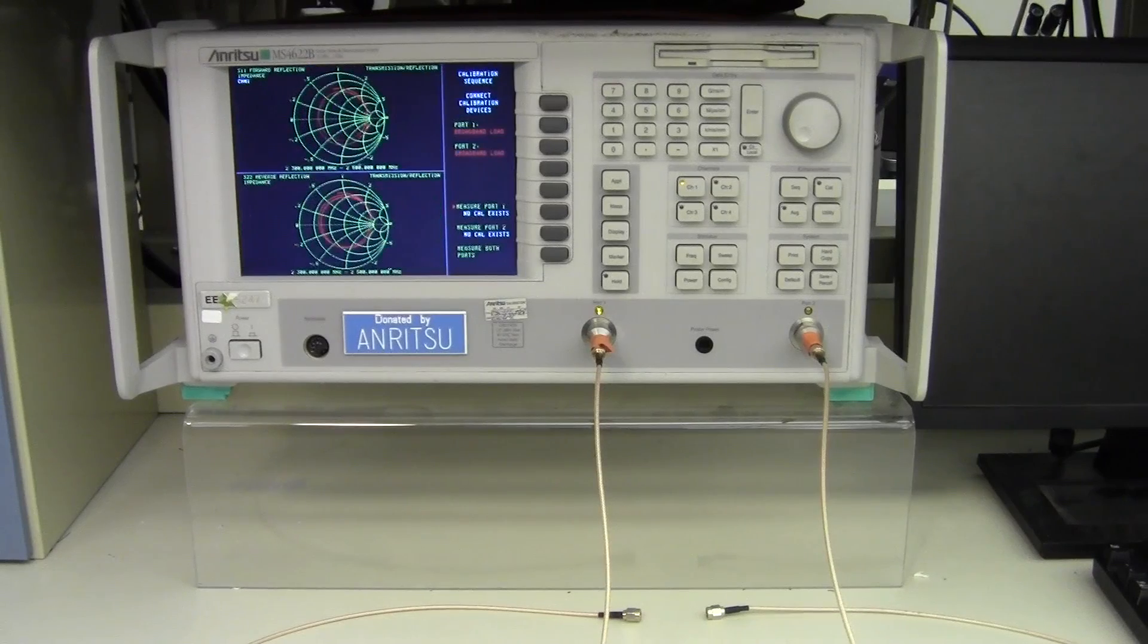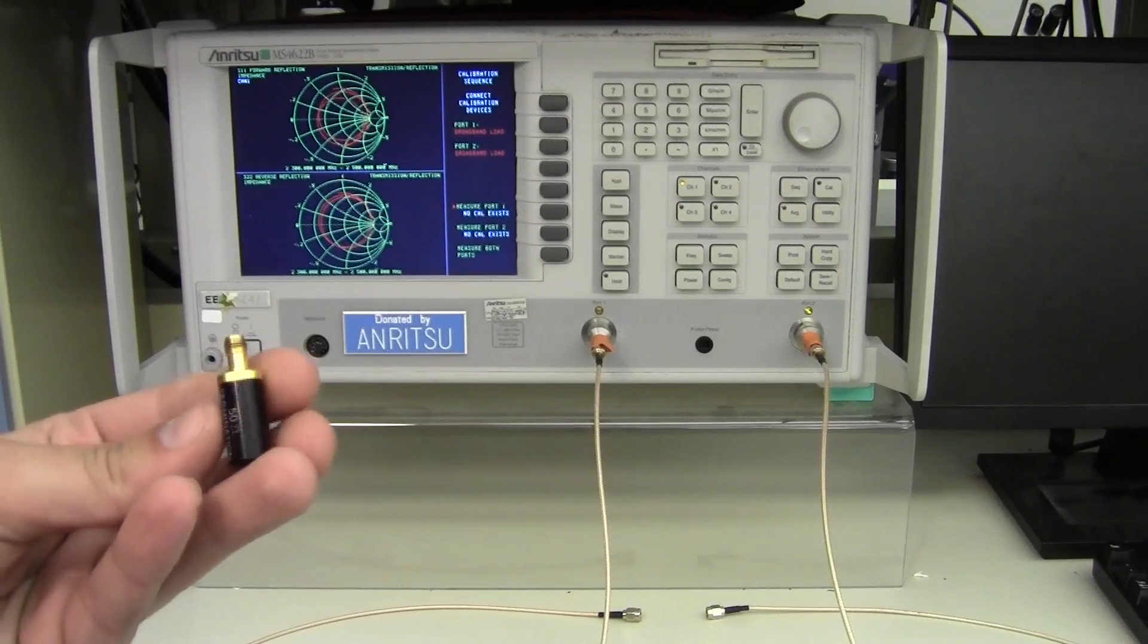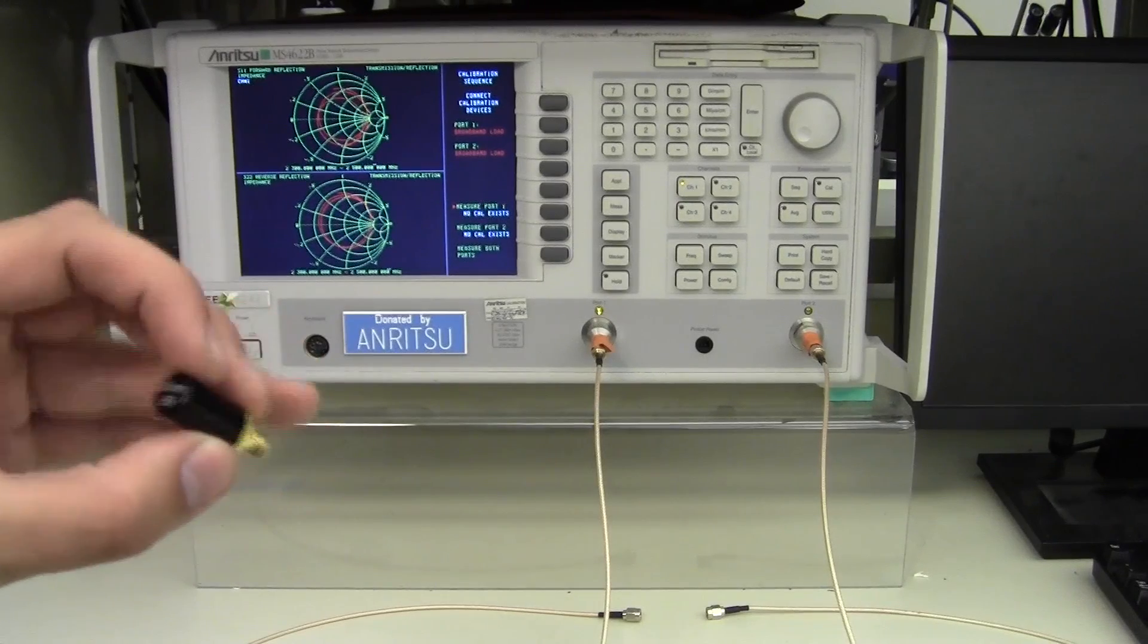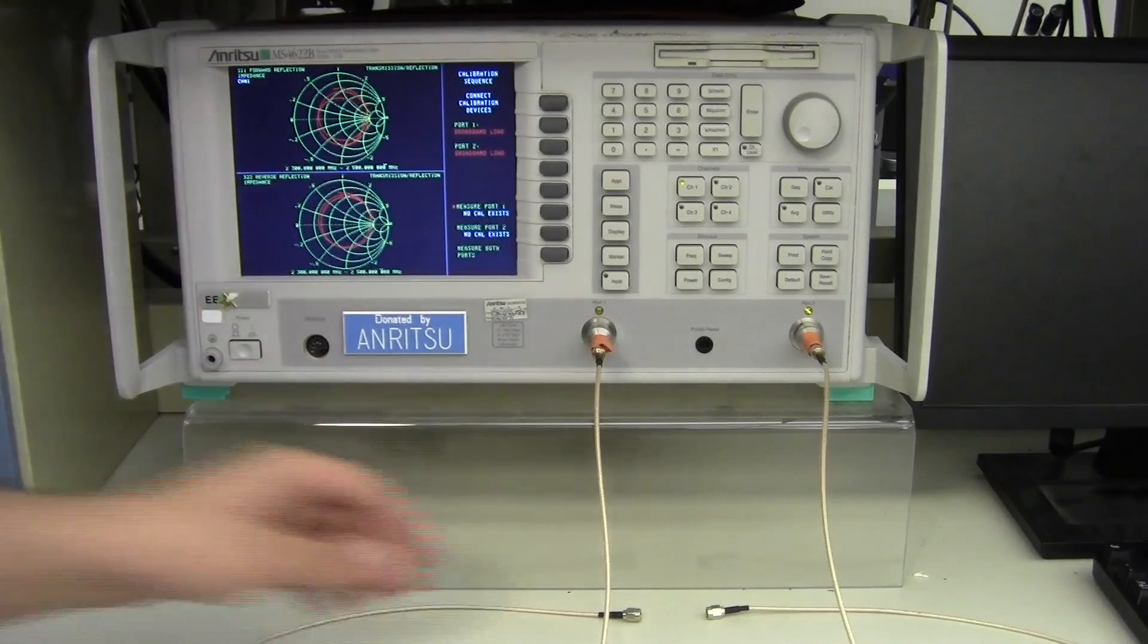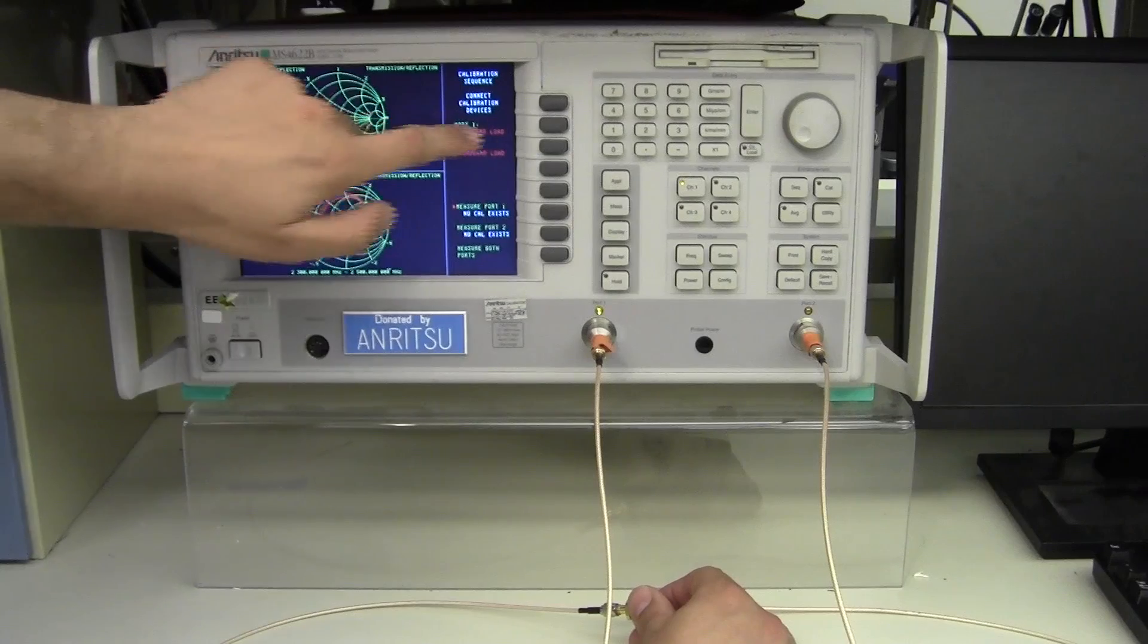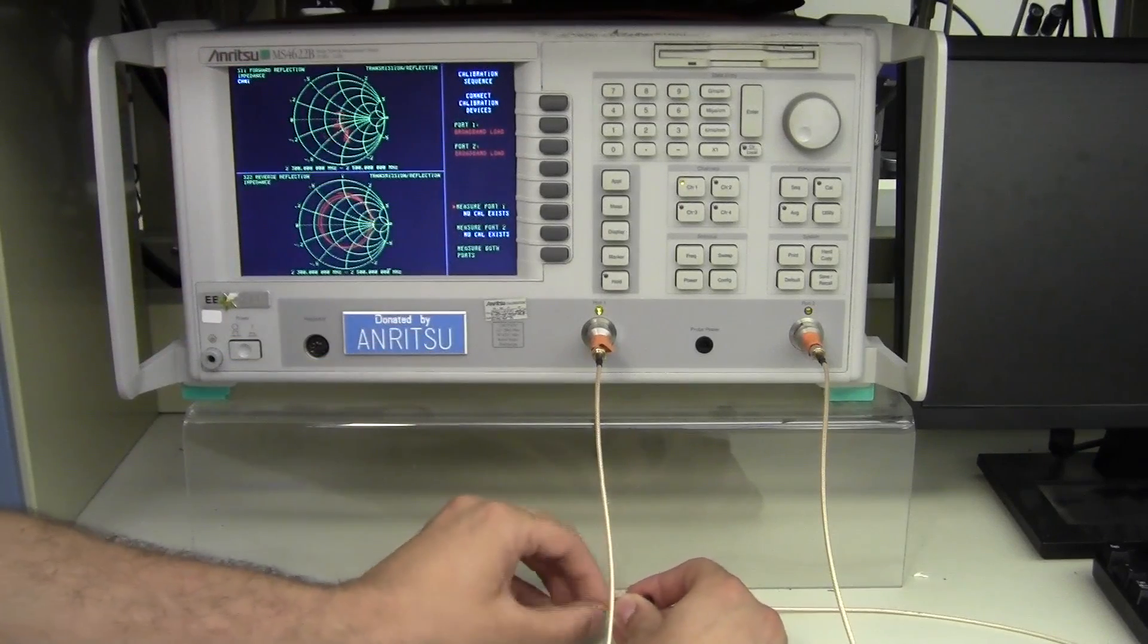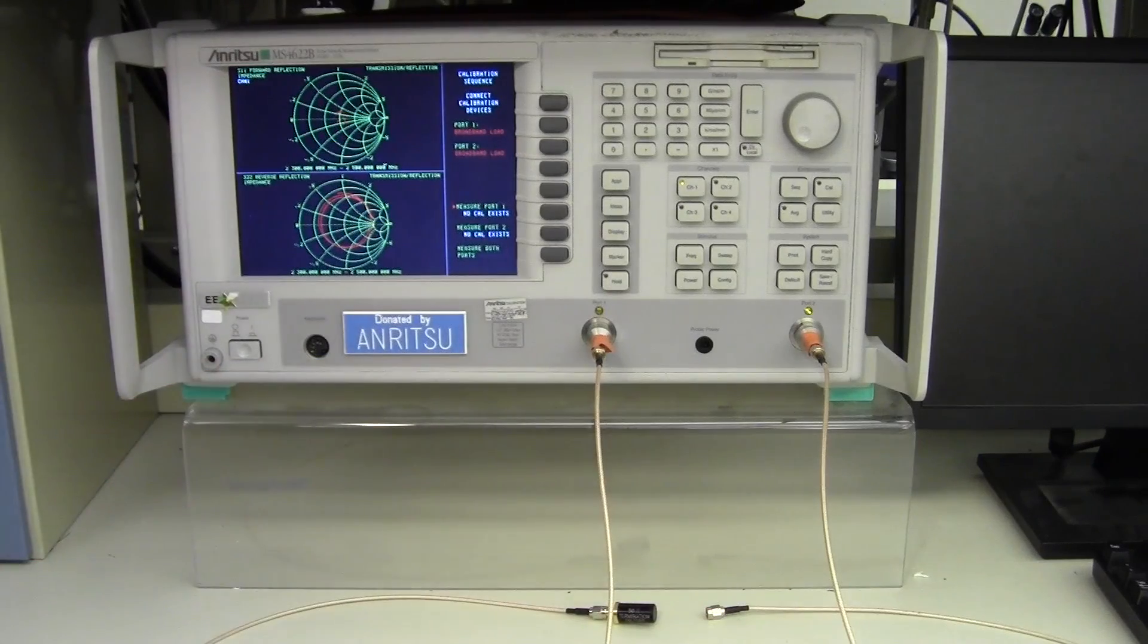We now can start the calibration. The first step is calibrating the two ports with a broadband load. This is a 50 ohm broadband load, which is possibly the most expensive 50 ohm resistor you ever use in college. On the top right here it asks port 1 broadband load, port 2 broadband load, and so I will install on each of the two ports a 50 ohm broadband load.